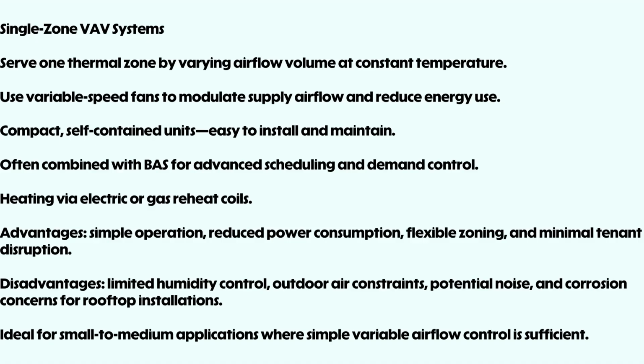Finally, single-zone VAV systems regulate airflow to one zone, using variable fan speed control while maintaining constant air temperature. This allows precise control of load with minimal energy waste. Advantages: lower fan power consumption. Smooth modulation of airflow based on demand. Factory-assembled packages with advanced controls and BACnet integration.